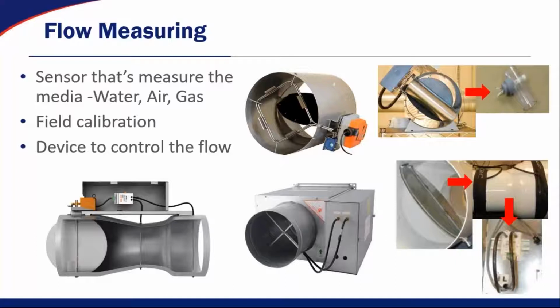And usually there's some type of device to control the airflow. In these examples, these are some of the popular ones that are out there. You can see a flat edge blade damper, a bifurcated butterfly valve, and a couple of different variations of Venturi flow measurement with a blade damper that's out in the field right now.